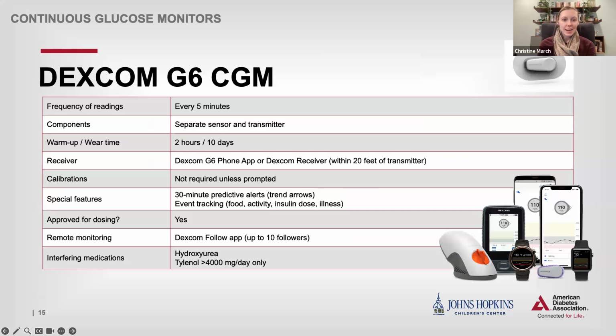We'll start with the Dexcom G6 continuous glucose monitor. The G6 gives you a sensor reading every 5 minutes. This sensor has a separate transmitter, which is changed every 3 months, whereas the sensor itself is changed every 10 days, and that's important to know. If this system were to fall out while the child was in school, it would be important to make sure the transmitter gets home so it can be reused.